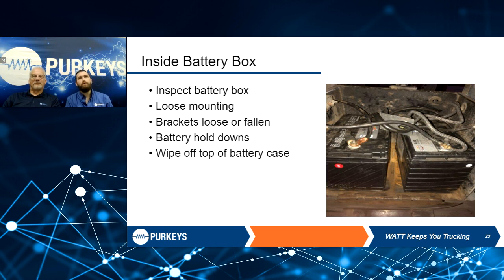When you are doing your PMs on your battery boxes, we need to first make sure that there is nothing floating around, because if any of those components start to arc, whether it be the circuit breakers, or if we swapped batteries and forgot to connect this up, now we're looking at our system not charging, or it could provide intermittent charging because it's not getting the proper connections.